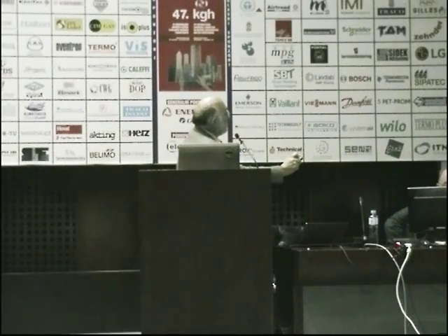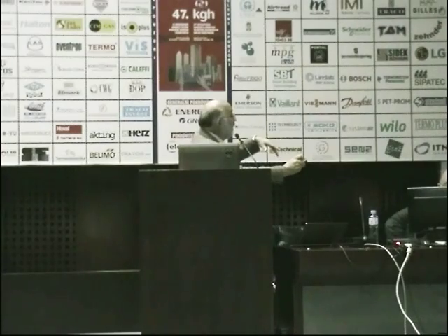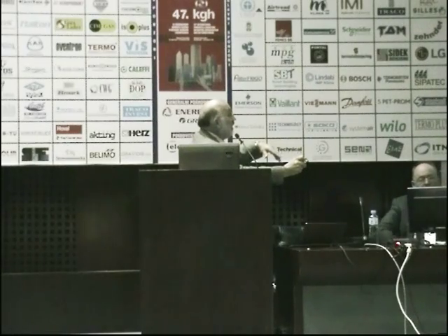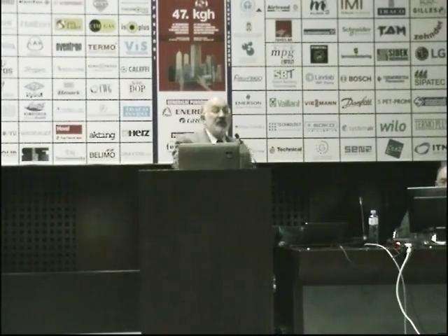And this here is mass flux as a function of quality. And now the process in the tube, mass flux is always constant. And then we can see either a stratified flow regime when the mass fluxes are low, or stratified wavy. And then we have intermittent plug slug. Then it goes to annular, and sometimes at very high mass fluxes, the flow regime map predicts mist flow.